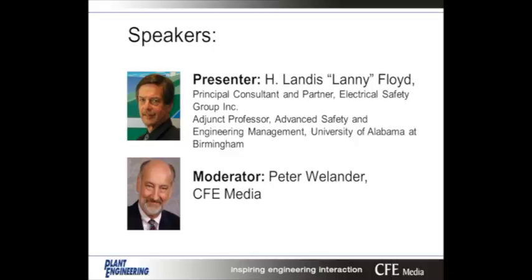Now, 70E also allows for an exemption: if the work is troubleshooting or diagnostic testing, the live work permit may not be required. However, other things have to be in place for that exemption - it has to do with the person's competency, standard practices in place, the hazard analysis conducted, and the PPE selected. So although the energized work permit may not be required, the level of detail to ensure the work is done appropriately is really no different.